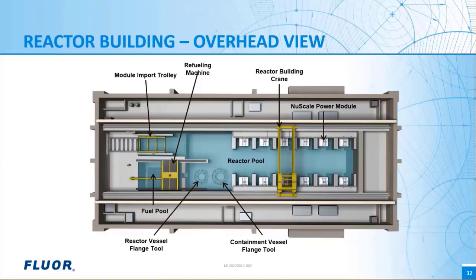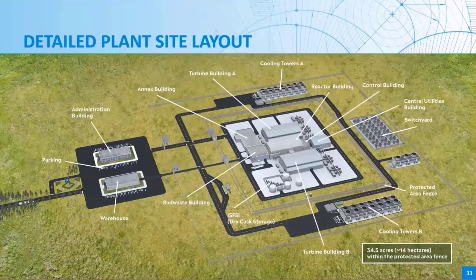Refueling machine does all of the fuel handling. All the fuel offloading and unloading is done, as I said, at the bottom of the reactor pool. And the fuel pool is separated from the rest of the reactor pool. And the fuel pool can hold up to 10 years of used fuel. Once the fuel is cooled for several years, the used fuel is then loaded into dry storage casks and dry stored on a used fuel storage pad within the plant security perimeter, which I'll show you here in a minute.